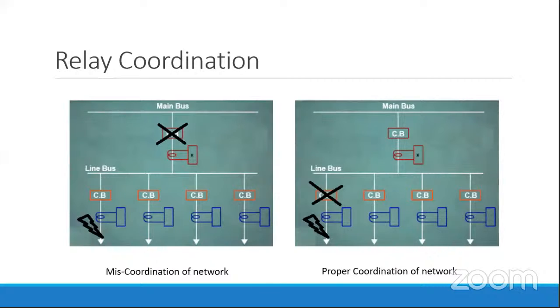So let's move further. Relay coordination. Here you can get a better idea of what the term relay coordination actually means. You can see a typical diagram where the main bus is feeding the network, and there are outgoing feeders going to certain locations. Now, the term relay coordination means that if any fault occurs in the first feeder, then the circuit breaker associated with this feeder should isolate it, not the incomer feeder.